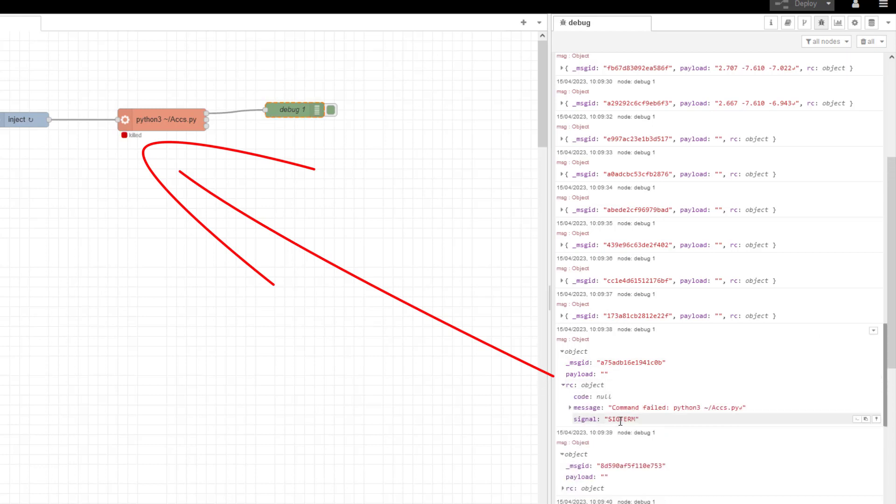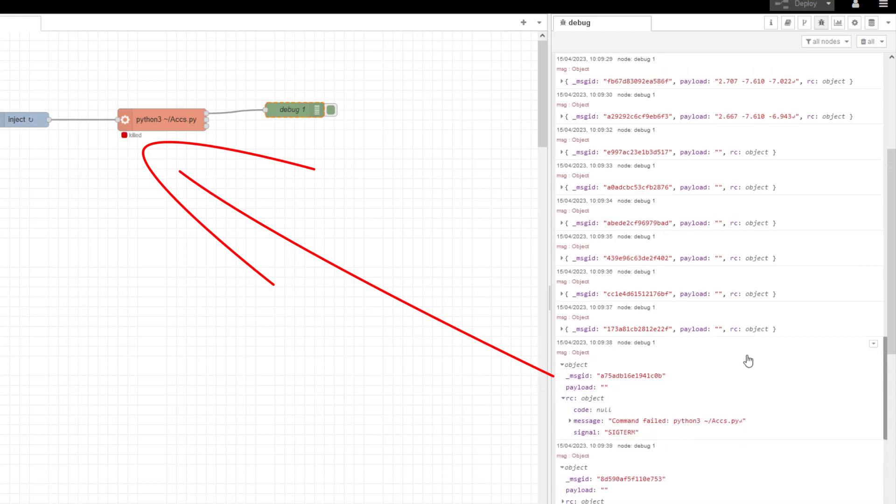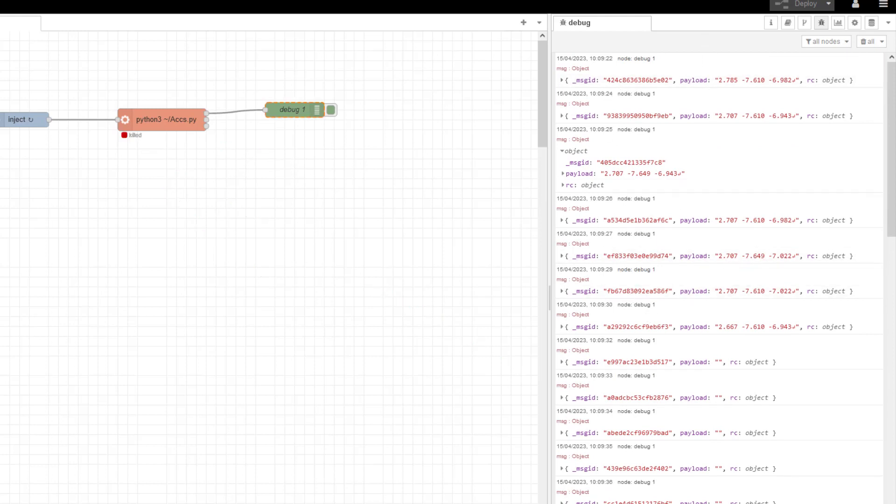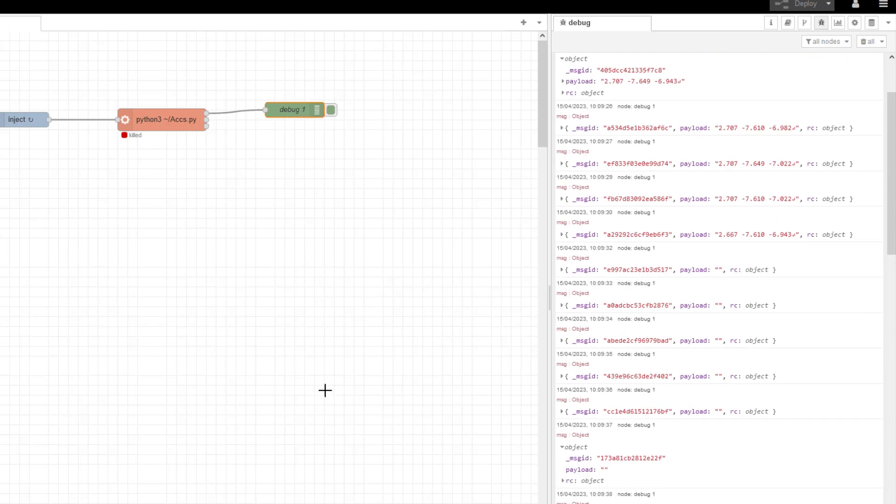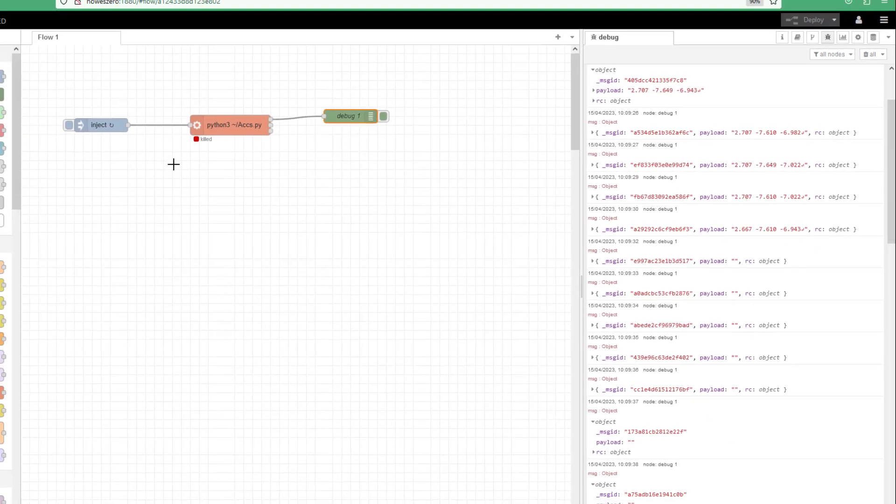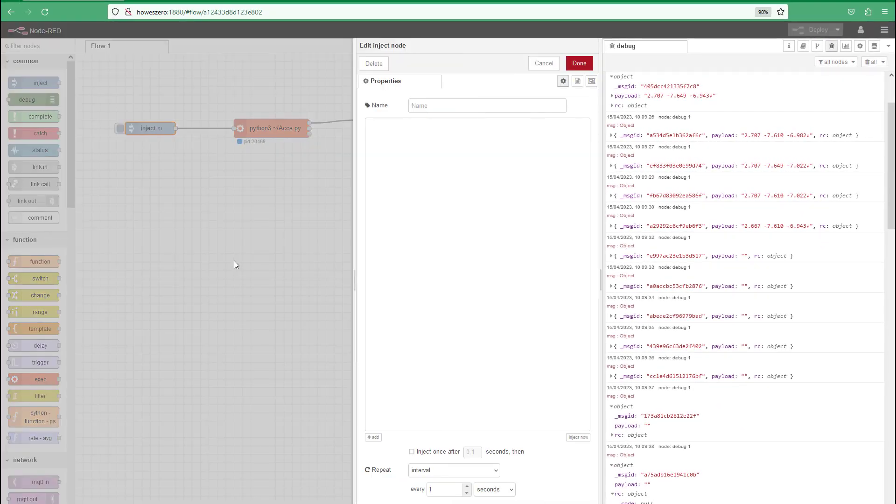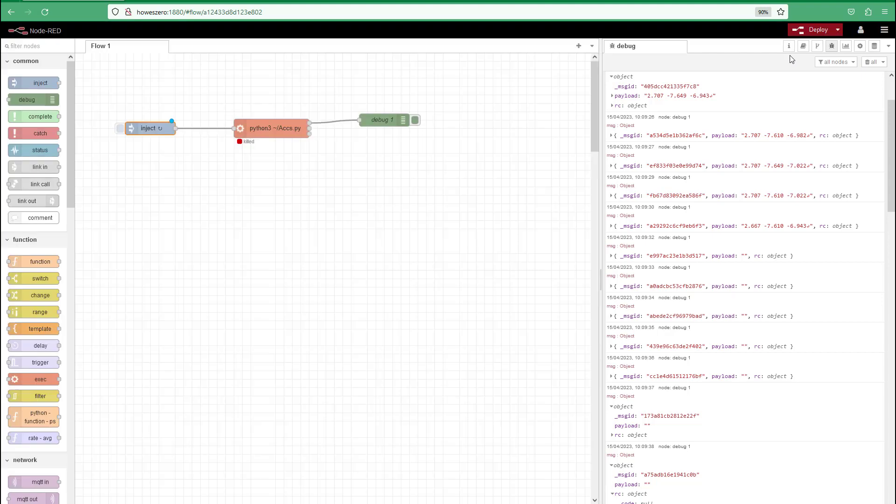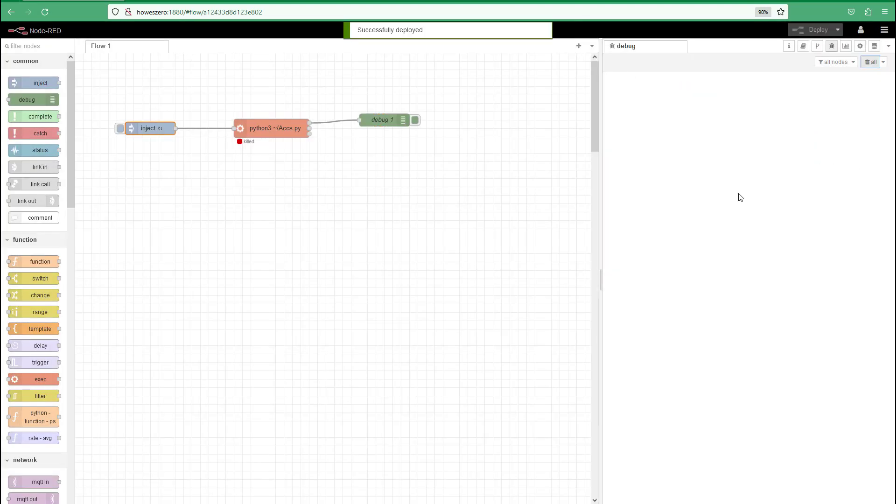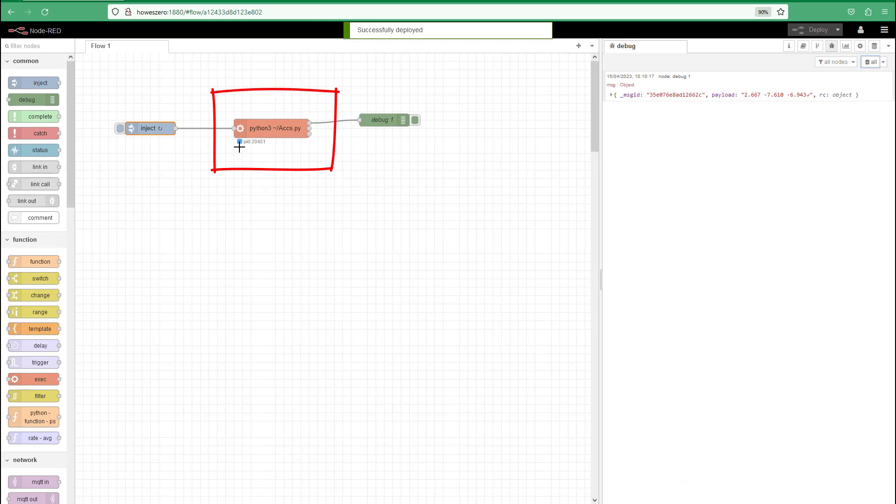But I really want to try and take advantage of the speed. I don't want to start having issues with communications. And you can see here I'm getting some comms errors. Because I'm pulsing this too fast. It's taking too long to start up. So I can't go one second. Let me deploy that. And then we'll clear all of that. So let's see if that gets rid of my red here. So I've had to slow it down.